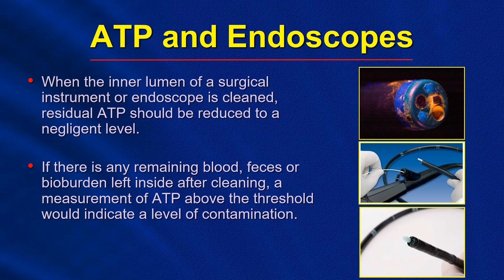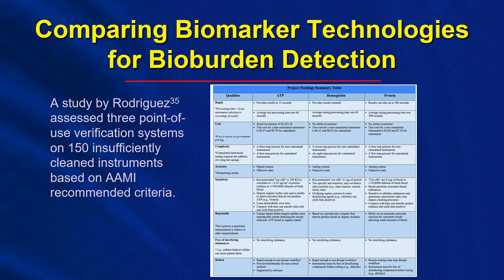This study compared actually three methods of verification using AAMI set criteria. They used ATP, hemoglobin tests, and protein tests. Now, the ATP test achieved the fastest processing time, had the lowest long-term cost, and was the only system that met objectivity criteria. Lastly, the ATP system's ability to test non-critical surfaces, in addition to surgical instruments, shows the system's versatility and potential to impact clinical settings that do not reprocess instruments and equipment.